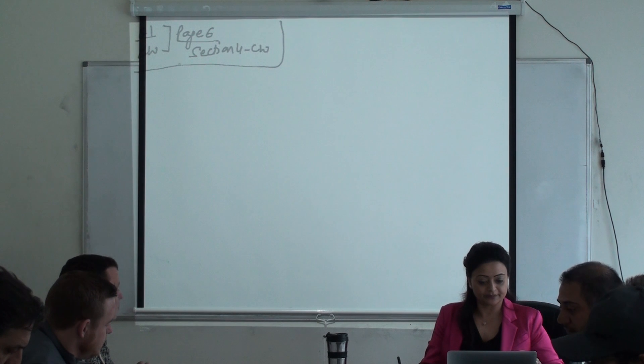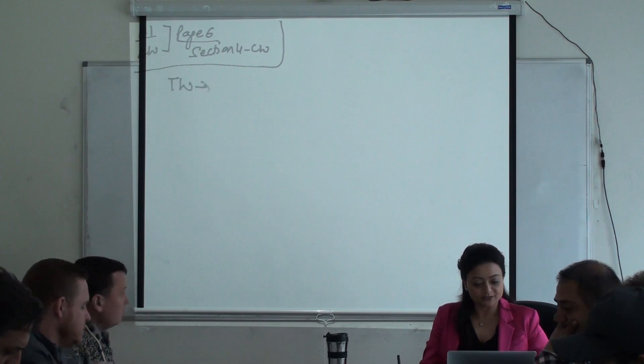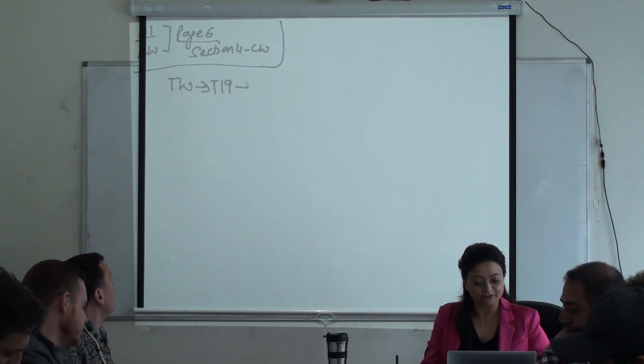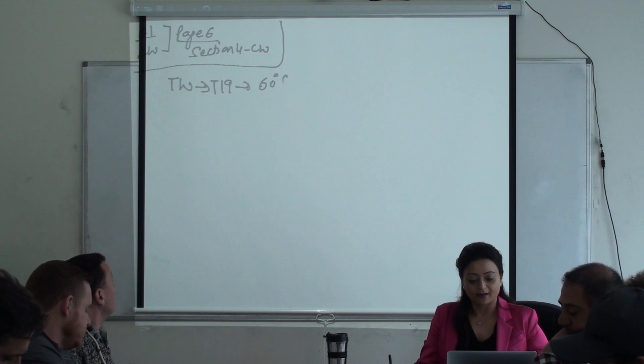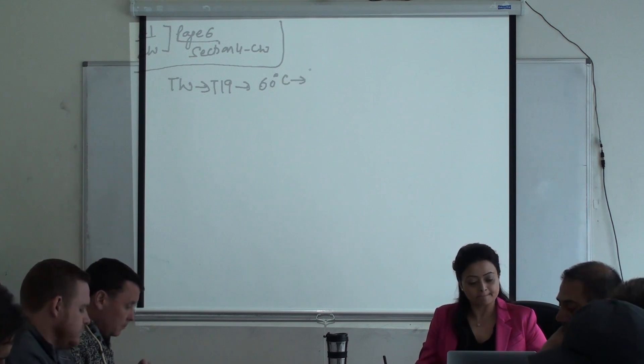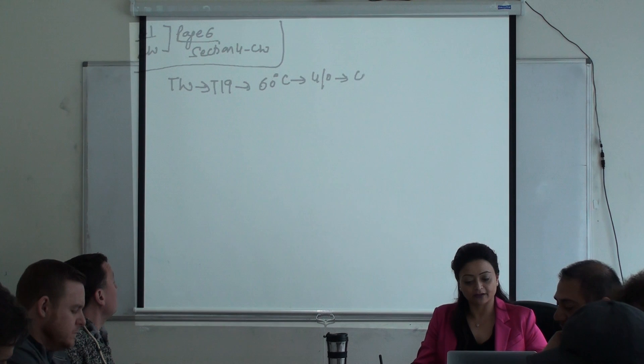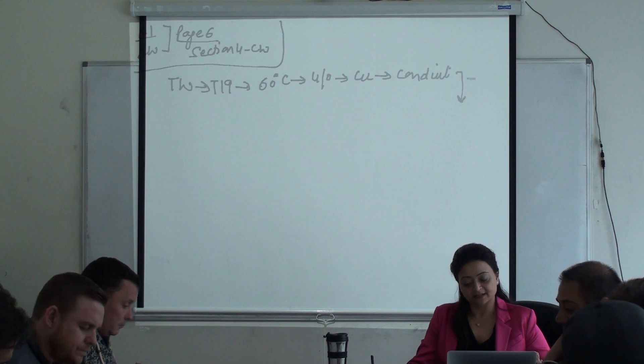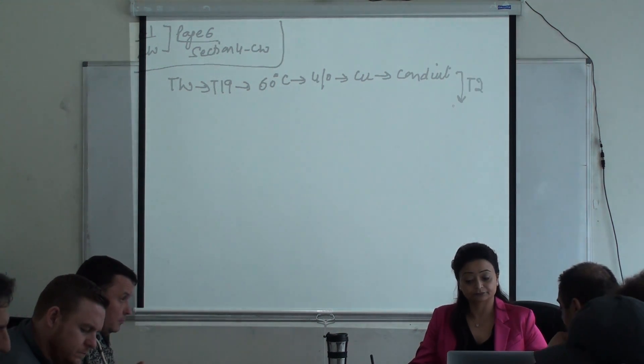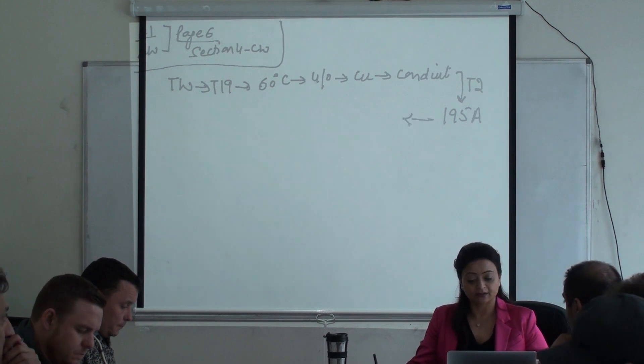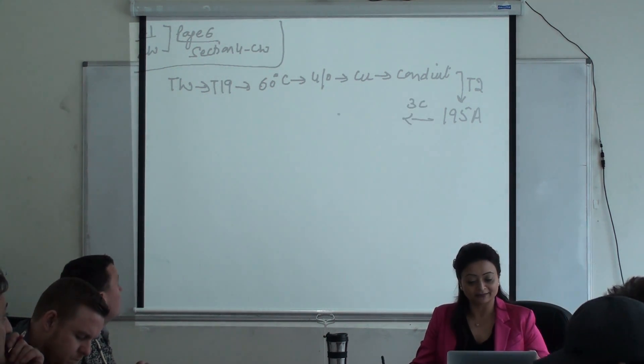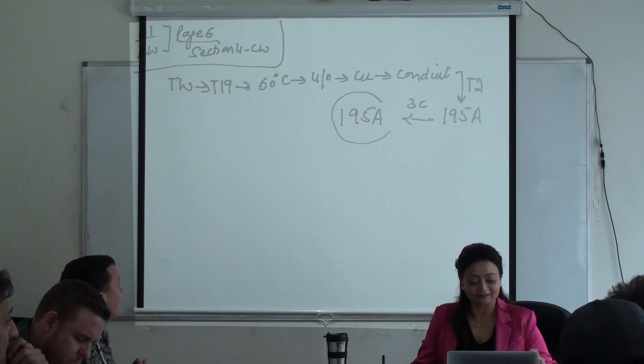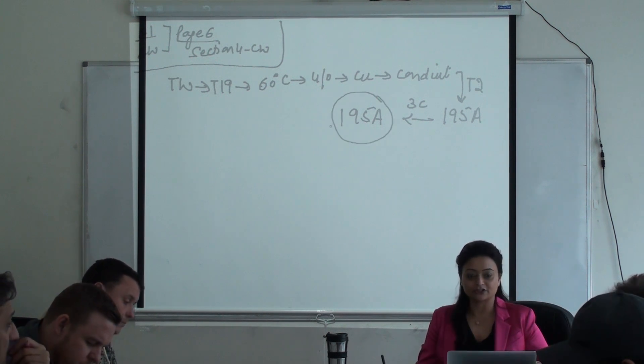It's given TW, which based on table 19, you guys know it's good for 60 degree C. What is the conductor size? 4/0, copper or aluminum? Copper. Free air or conduit? Conduit. So we go to table two. What's my ampacity? 195. And how many wires? Three wires. So no derating factor, answer stays at 195.